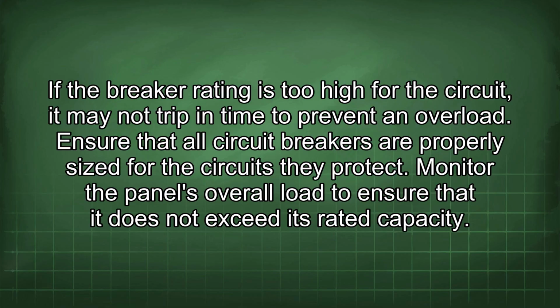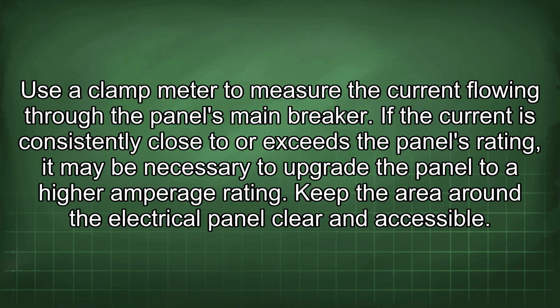Monitor the panel's overall load to ensure that it does not exceed its rated capacity. Use a clamp meter to measure the current flowing through the panel's main breaker. If the current is consistently close to or exceeds the panel's rating, it may be necessary to upgrade the panel to a higher amperage rating.